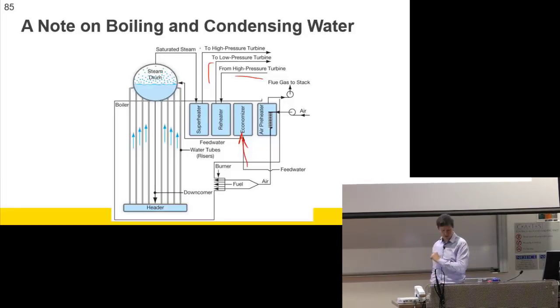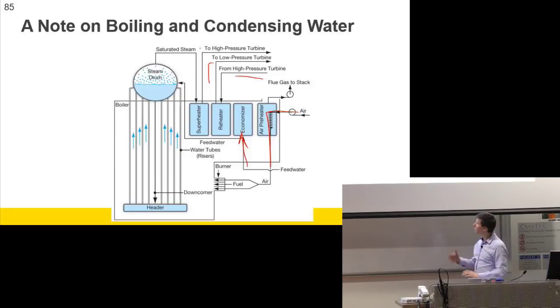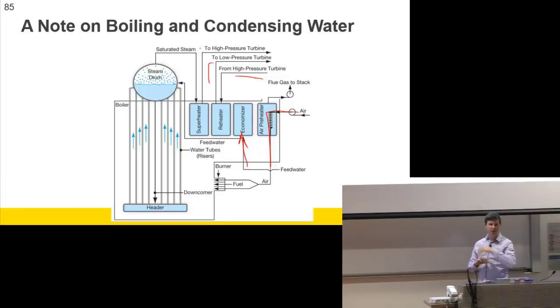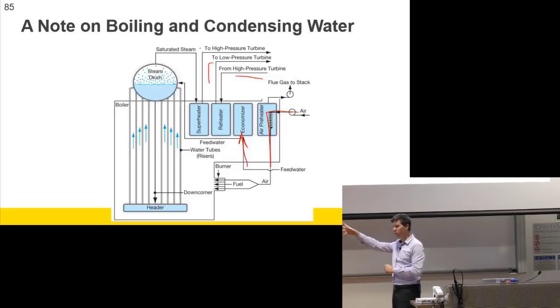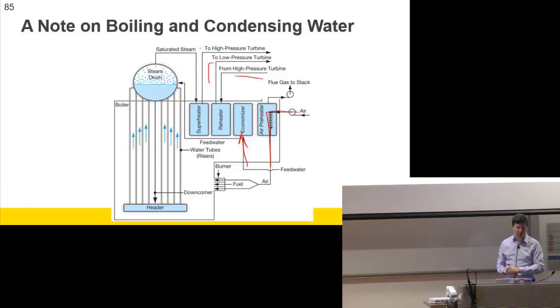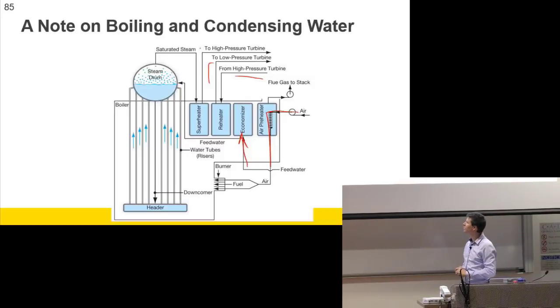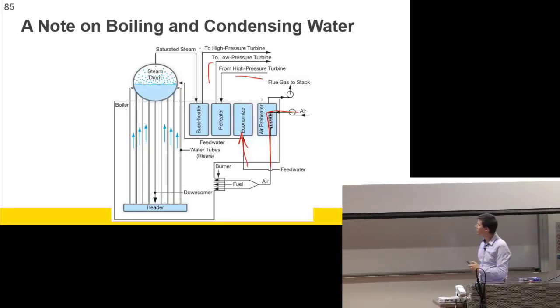And then the other thing they're doing here is taking their incoming air through and preheating the incoming air. So here you're dealing with air and air, right? But the thought is, if you can preheat your incoming air by 100 degrees, so rather than drawing it in at 20 degrees, you're drawing it at 120 degrees, then that's fuel you don't have to burn at the base. So if you can cool your stack gas down as much as possible, you want the coldest air leaving the stack as you can get by drawing all of the energy out. So you can get some complicated arrangements to try and achieve those superheated states. Cool.